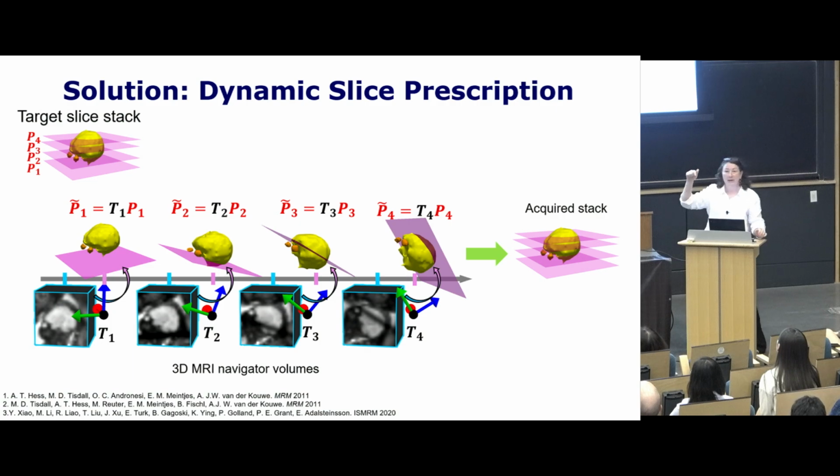It turns out that because of the energy constraints on fetal imaging, which are pretty strict, there are 1.5 seconds of dead time between every 2 slices, because enough energy gets deposited in acquiring each one of these slices that you have to cool down before the next slice is acquired. And so the 1.5 seconds is to acquire the image, estimate the fetal head pose, and tell the scanner to change what it's doing. These volumes take 1 second to acquire. They're about 5 millimeter isotropic resolution, and the contrast is terrible.